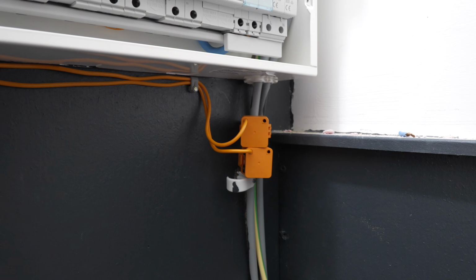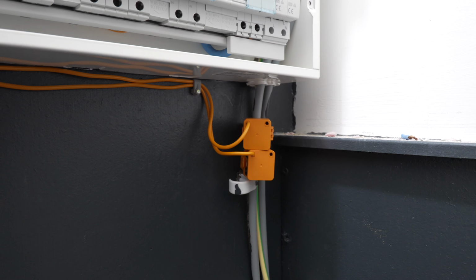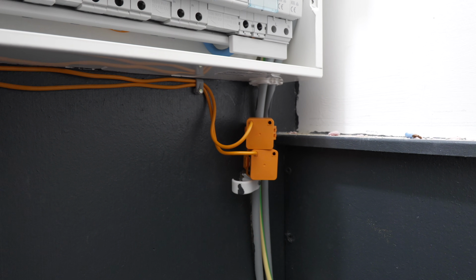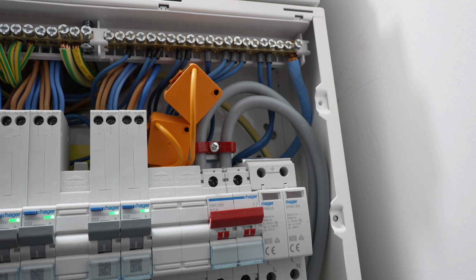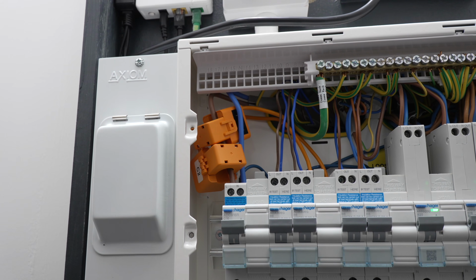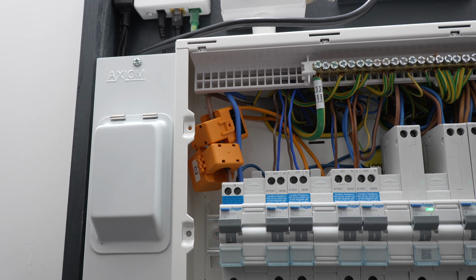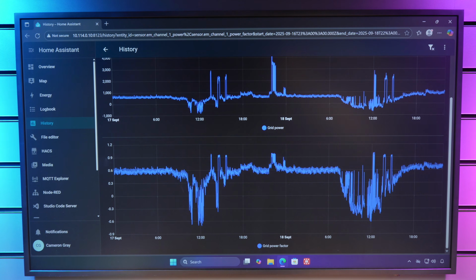So I have two CTs on the grid connection. Those are wired into A1 and A2 on the energy monitor. The two CTs on my socket circuit are wired into B1 and B2. And the two CTs on my solar circuit are wired into C1 and C2. And having done that, the results are now completely stable.